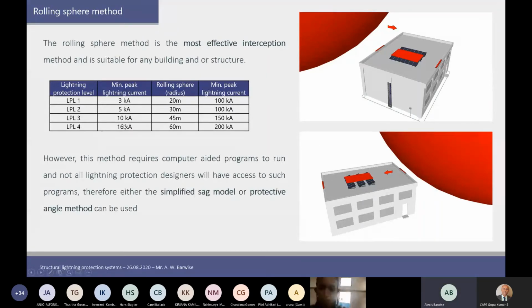In the IEC standard, we see that for certain levels of protection, 1 to 4, we have a bandwidth of lightning currents which we can then intercept. So basically we are fail-proofing the system. So for a lightning protection level 1, any lightning current above 3000 amps will be captured or will be caught by the system. The lightning protection level 4, as an example, will start only from about 16 kA. And this is where I've had great and very insightful chats with the Vaisala group, where we start seeing data coming back from African countries as to the average minimum peak values, because this will determine our protection levels. But let's carry on, and I'll show you what we are stating by this.